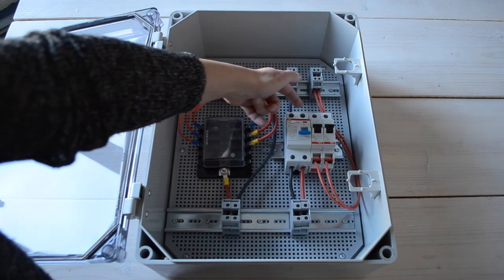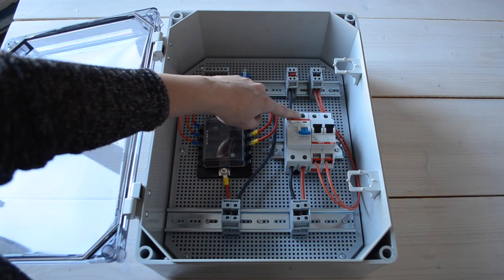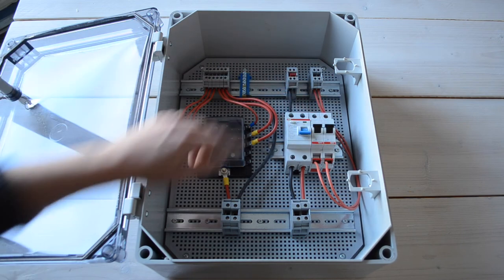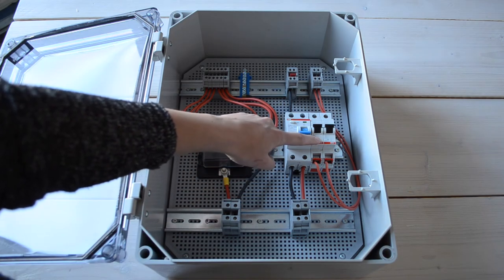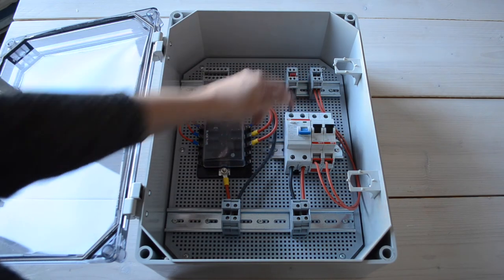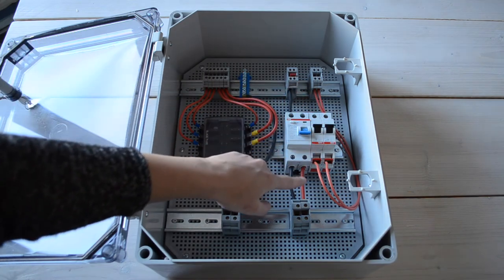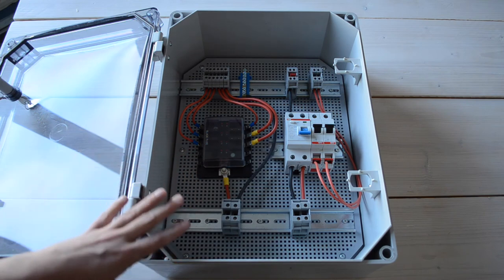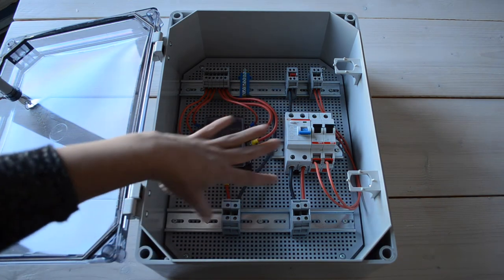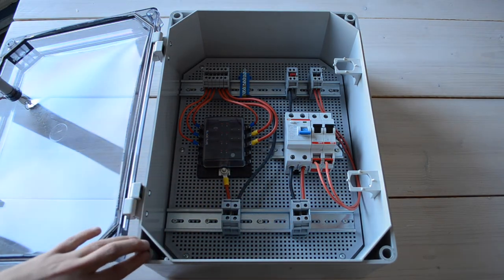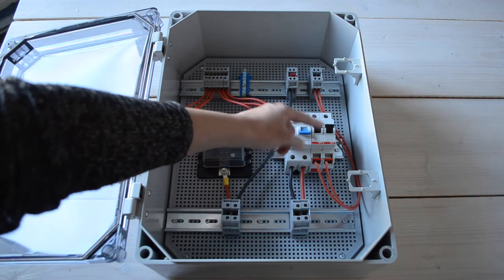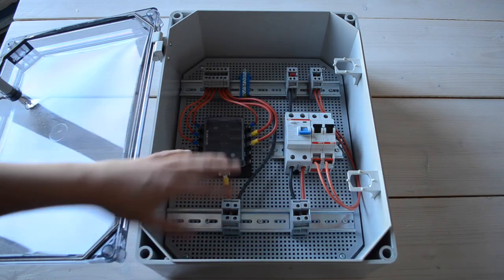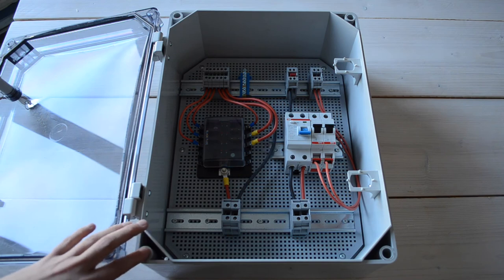The live cable will run up into this RCD. There is a small bridge up here that I will show you which is connected to both of these trips. That's why these trips are faced upside down because they can only be connected with such a copper bridge on this side. And that connects this cable back to these two. So this and those are the same cable basically but split into two. This is our 230V side and these two cables will be connected to our two plug sockets. Now these two trips are again switched off. It doesn't matter. There is nothing connected. They should be switched on downwards, this one upwards when we will be eventually using it.